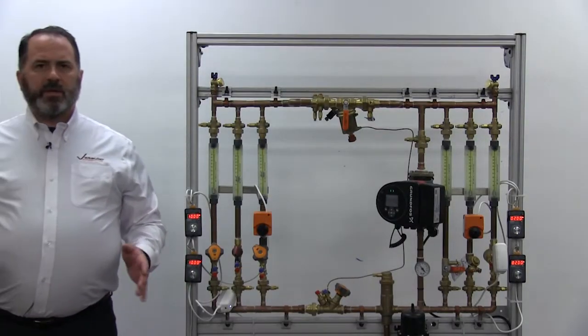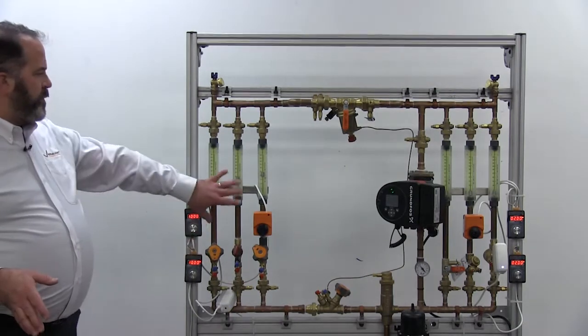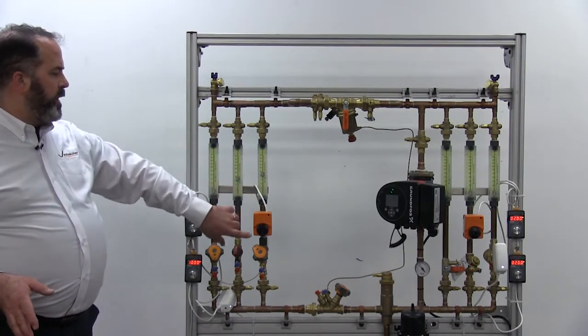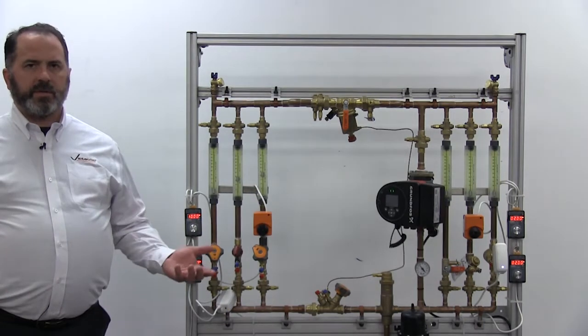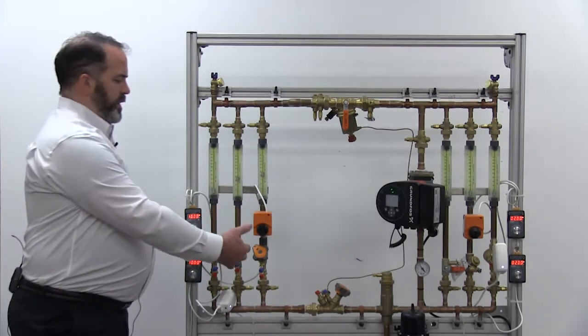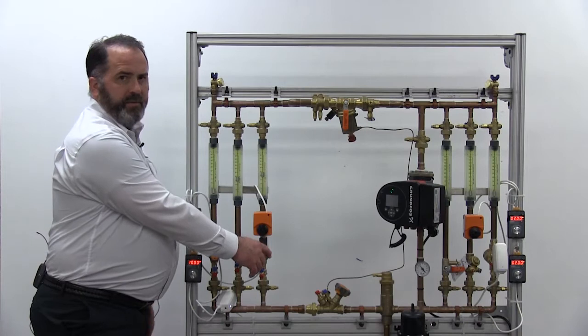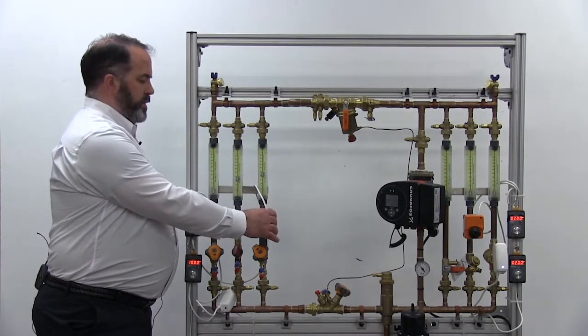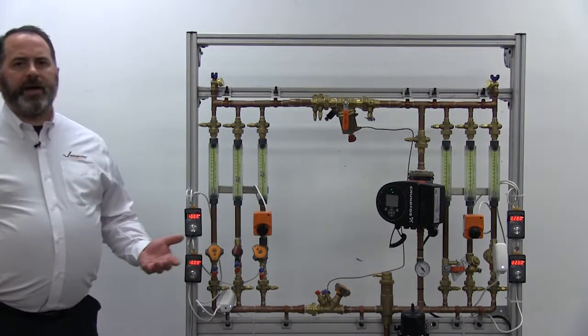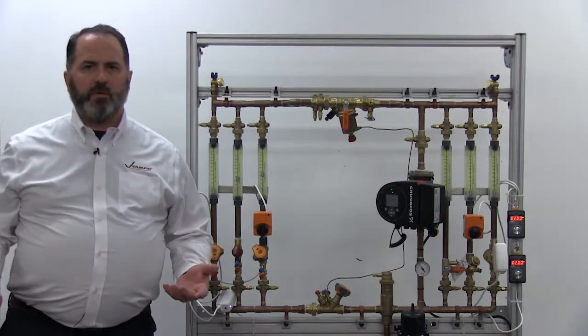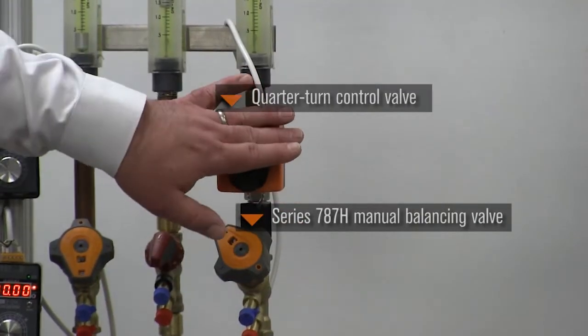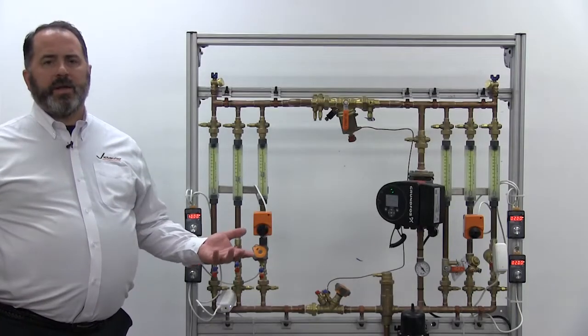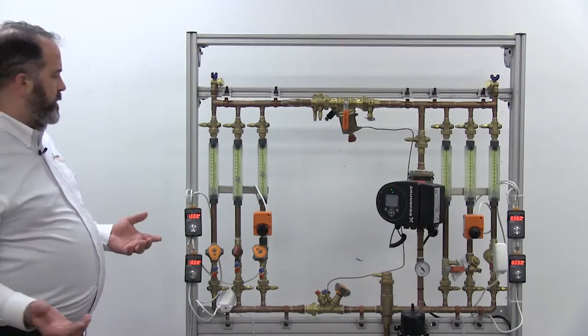Let's talk about two different control valve arrangements. On my loop, I have two branches currently running and on each one I have a different means of controlling flow through the system. The first one, I'm using a manual balancing valve and then a quarter turn ball style control valve to control flow through the system. So the manual balancing valve does the balancing, the control valve does the control. Pretty common application for systems like this.